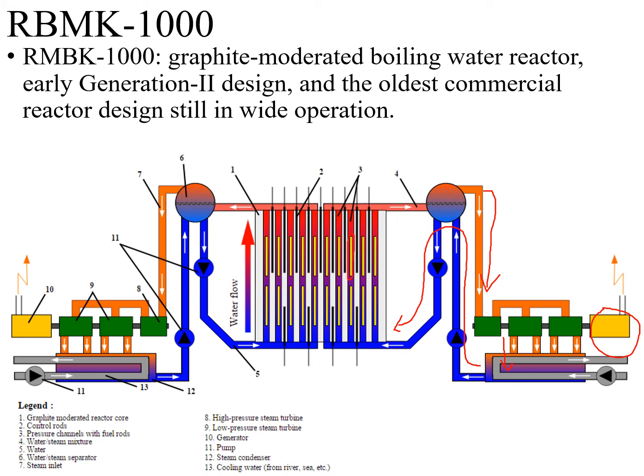The reactor uses coolant channels because the moderator is made of graphite. So this reactor is graphite moderated. You have the graphite surrounding each of those fuel channels to slow down the neutrons. This reactor is an early generation 2 design, and it is one of the oldest commercial reactor designs still in wide operation.